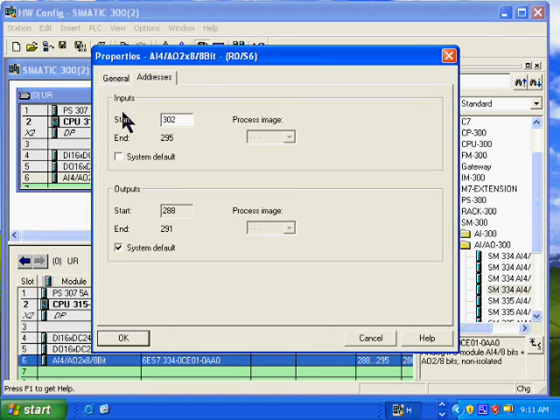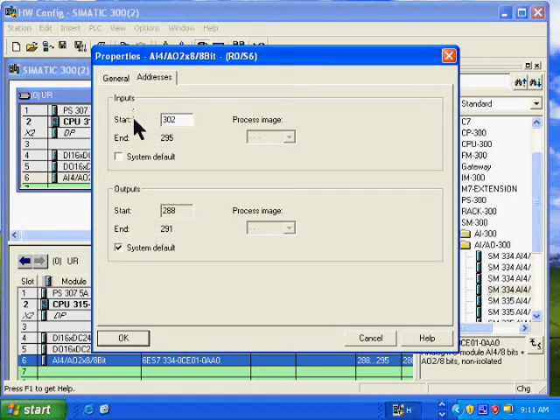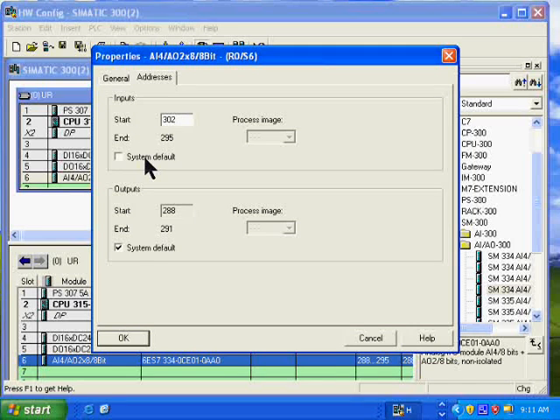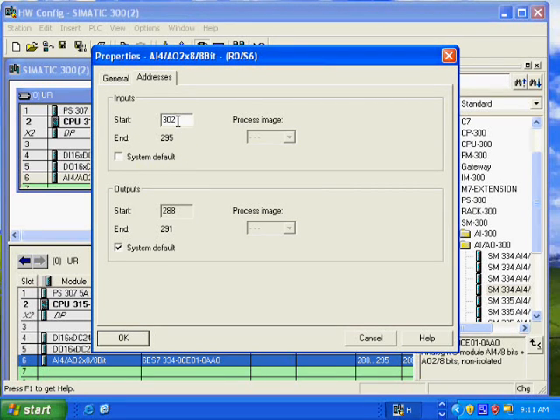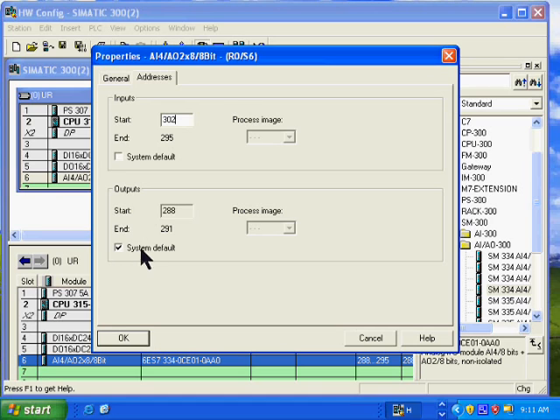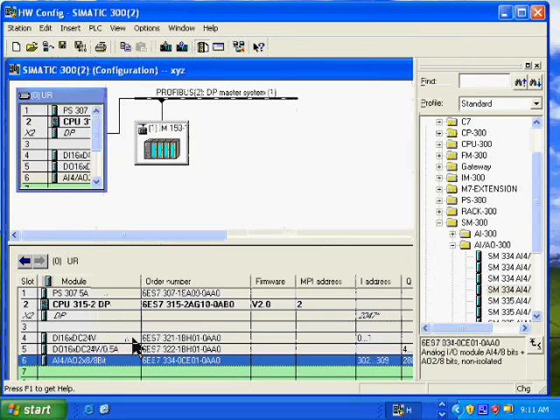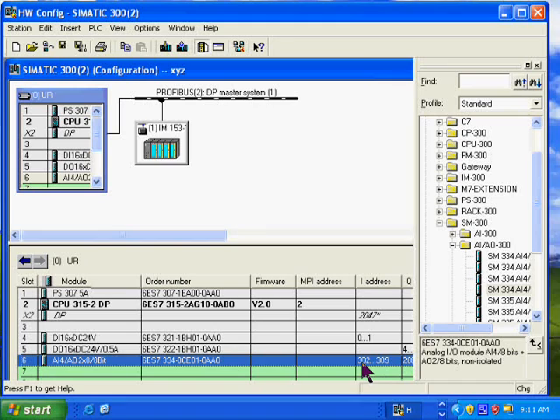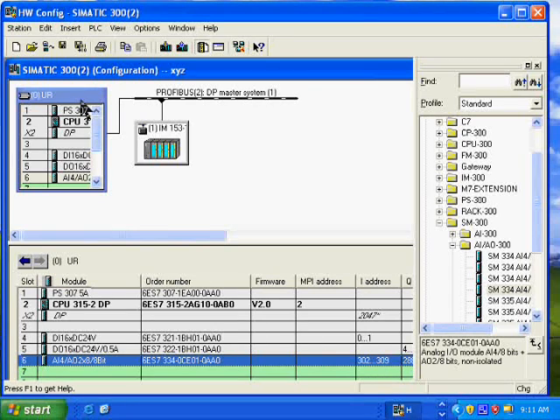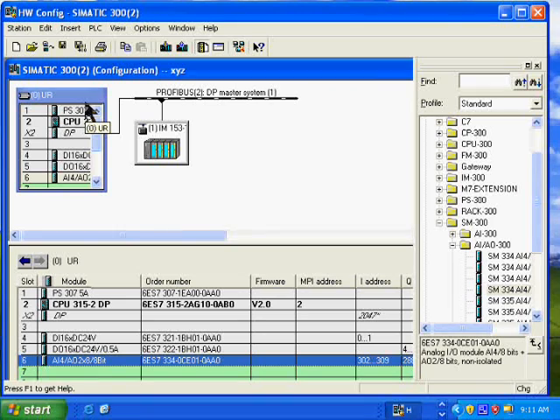In this example, I'm changing my default for my inputs, my analog input starting address, from system default to 302, where I'm using the system default for the outputs. I accept that by clicking OK, and it changes that address here, and now I can save and download this configuration to the CPU.